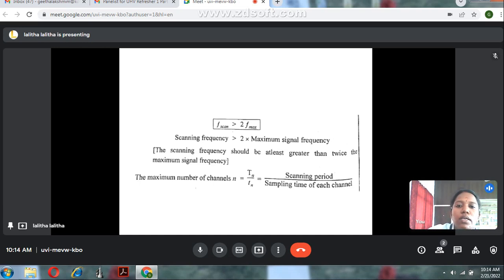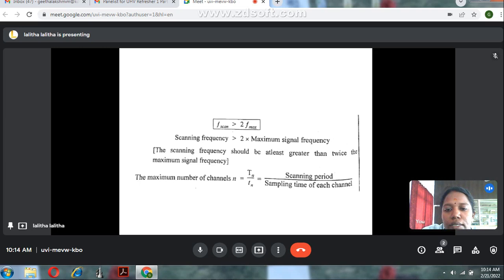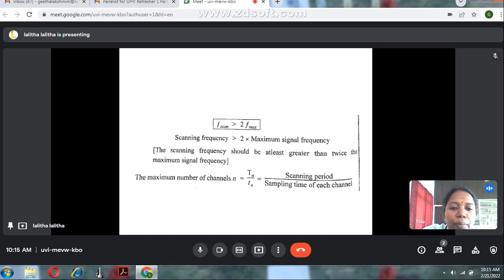The scanning frequency formula is: F_scan ≥ 2 × F_max, meaning the scanning frequency must be at least greater than twice the maximum signal frequency. The maximum number of channels n equals capital TN divided by small tn, where capital TN is the scanning period and small tn is the sampling time of each channel.